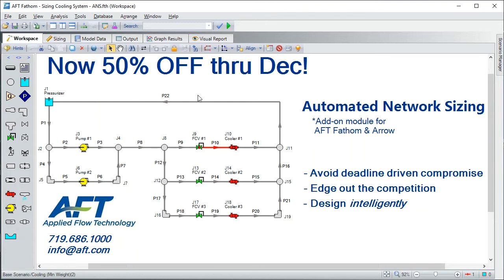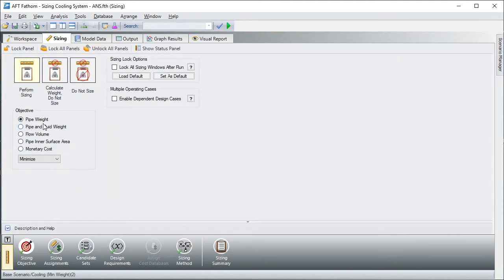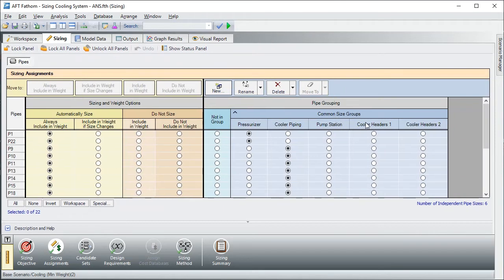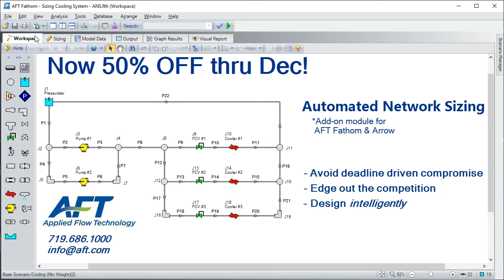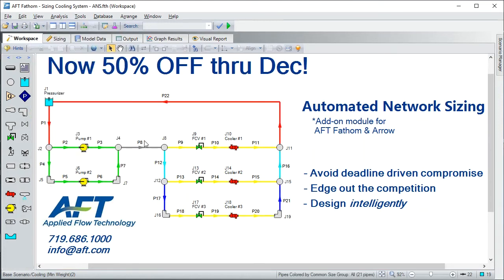Let's see what Automated Network Sizing has to say about that. We go to the Sizing tab — my objective is to minimize pipe weight. We also set up what we call common size groups. Intuitively, you know that in and out of a heat exchanger should be the same size pipe, or maybe the suction and discharge side of the pump. We've got the common size group set up.